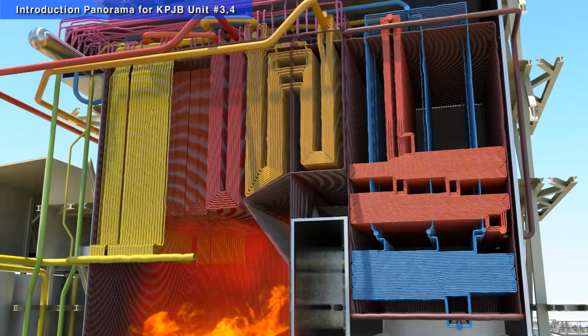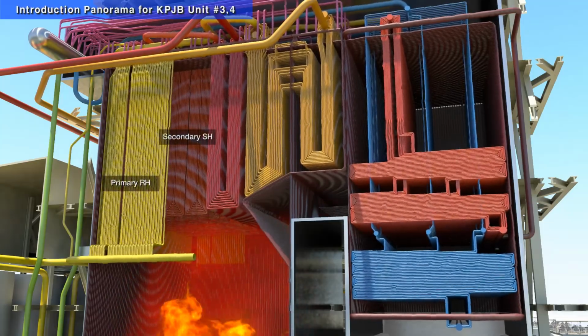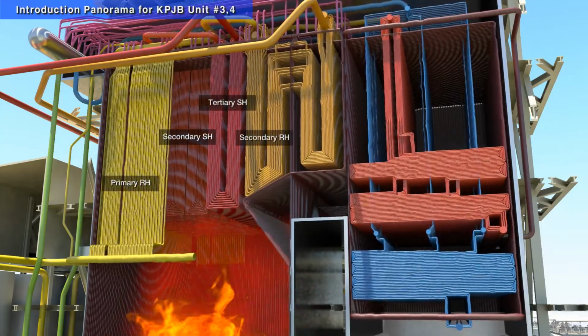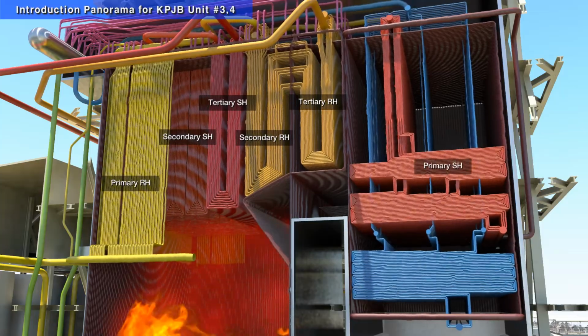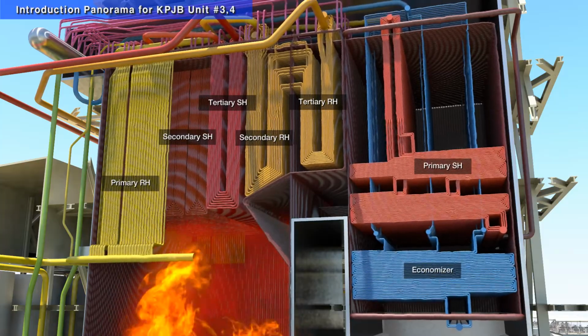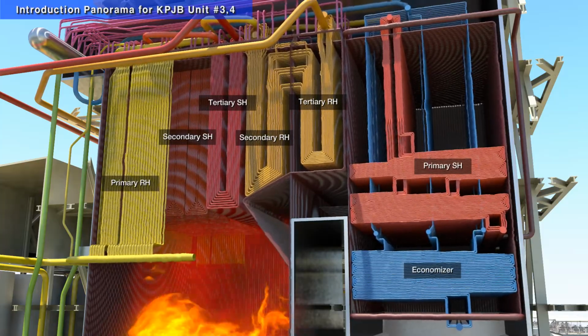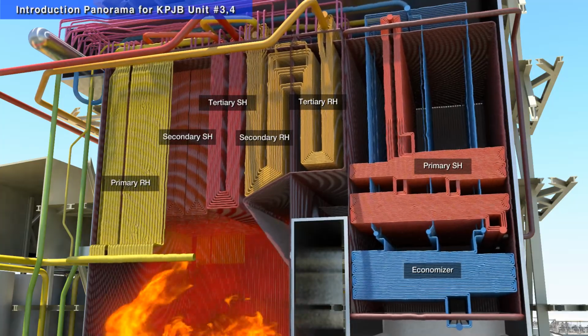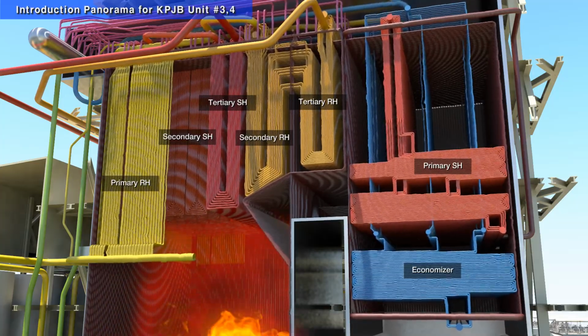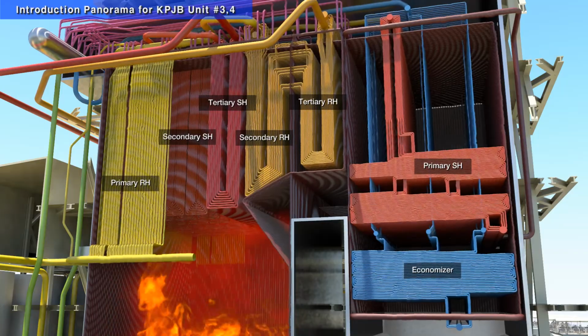The boiler's heating surface layout is in order of primary RH tube, secondary SH tube, tertiary SH tube, secondary RH tube, tertiary RH tube, primary SH tube, economizer, in the direction of the exhaust gas flow.